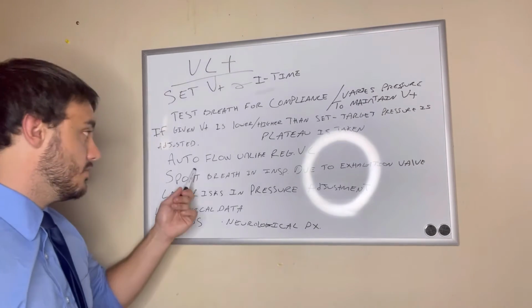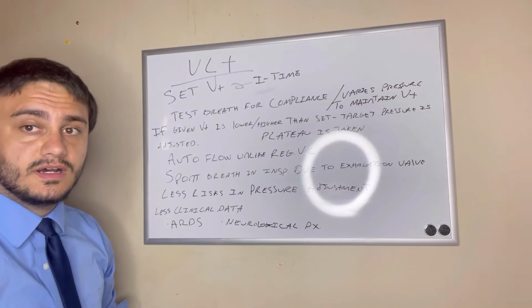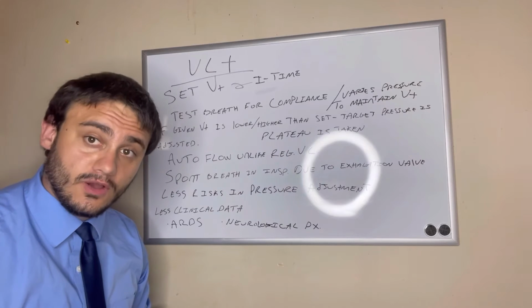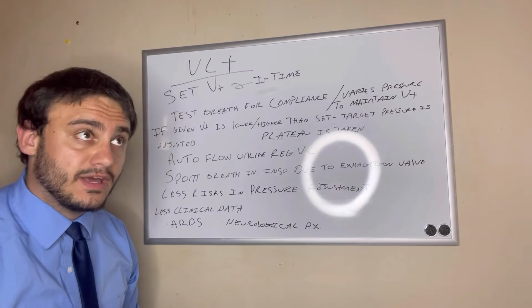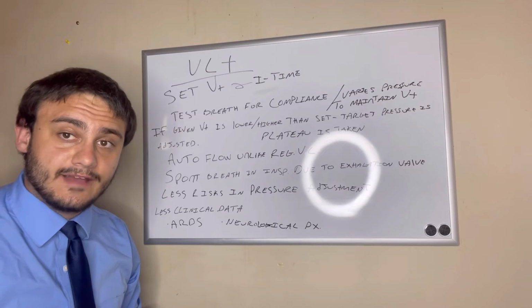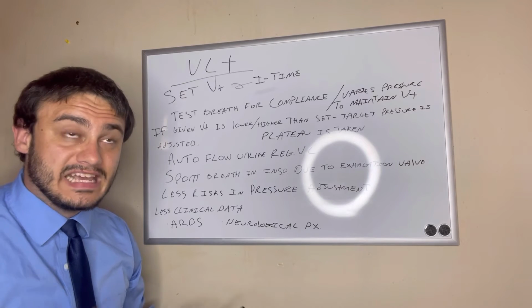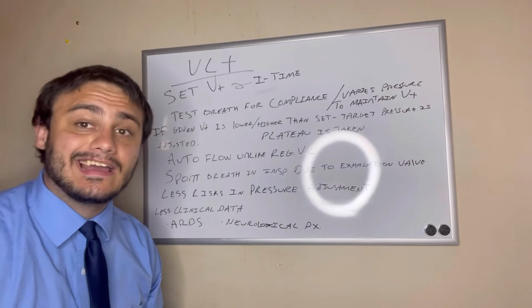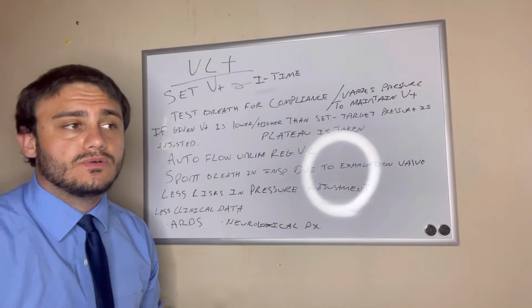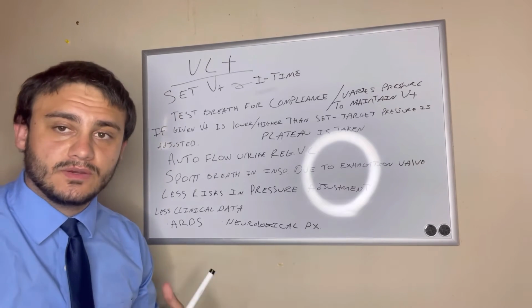And another name for volume control plus that I've heard is autoflow. That's because in regular volume control, you have a set flow. Let's say the flow set on regular volume control is 50. Well, no matter what, that patient is going to get 50 flow. So let's say that patient wants to take more flow. They can't. They can only take 50. Or they want to take less. So a patient can be air hungry if they want to take in more than 50 flow that's set on a ventilator.